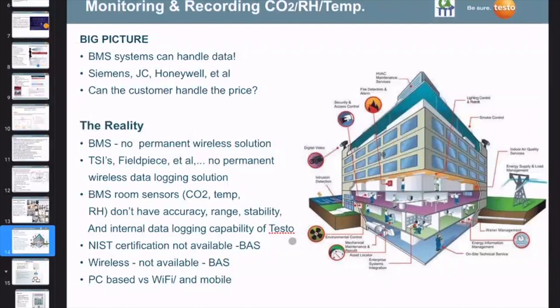Whereas Testo, we've manufactured data sensing technology for years, and it's really quite important that the system or the sensors that are going to be installed here at the school level really should be independent of the control aspect. Okay, that's a key thing. You don't want your controllers also being used to send and report the actual measured values in the space, because the point in fact is that most of these sensors and the controllers can change the display output to make it look more stable than what it might be. They can change the PID control algorithm to also make the room space temperature or relative humidity or CO2 numbers not quite reflect what is actually being measured.